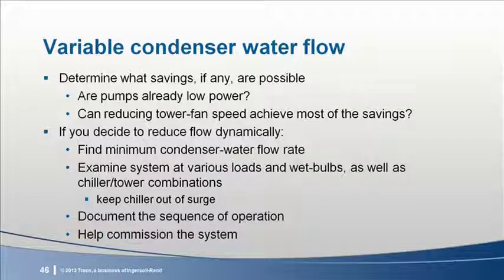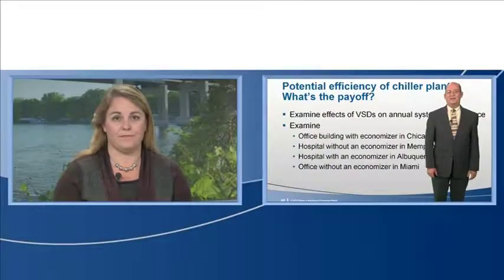But if you do decide to reduce flow, there are limits to consider, and Mick will be talking about that in a few minutes. Some of the limits include the minimum condenser water flow rate, not only from the chiller's perspective, but also from the towers and the pump's perspectives. As you examine combinations of load and flow rate, you'll need to identify limits that keep the chiller out of surge. And as we mentioned in 2011's broadcast, documenting the sequence of operation and assisting with the commissioning of the system should be required of anyone dynamically modifying the condenser flow rate.